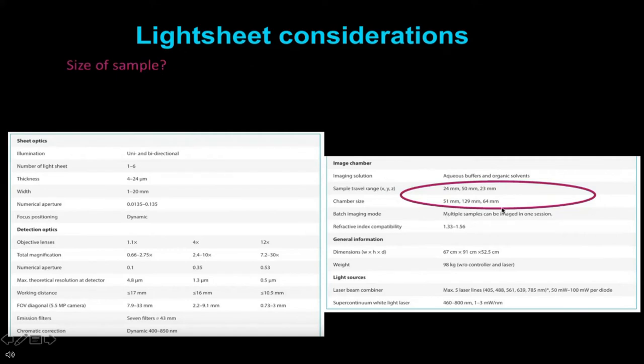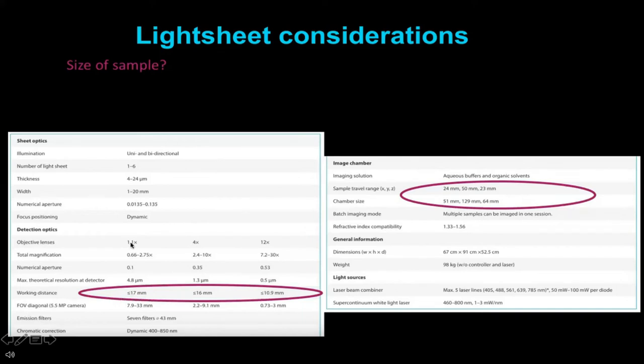In terms of sample size, you want to physically fit it into your chamber and check the travel range of the microscope. You also have to consider the working distance. For our 1x lens, the working distance is 1.7 centimeters, which is one of the highest working distances available at the moment. So you see how this varies with different lens magnifications.